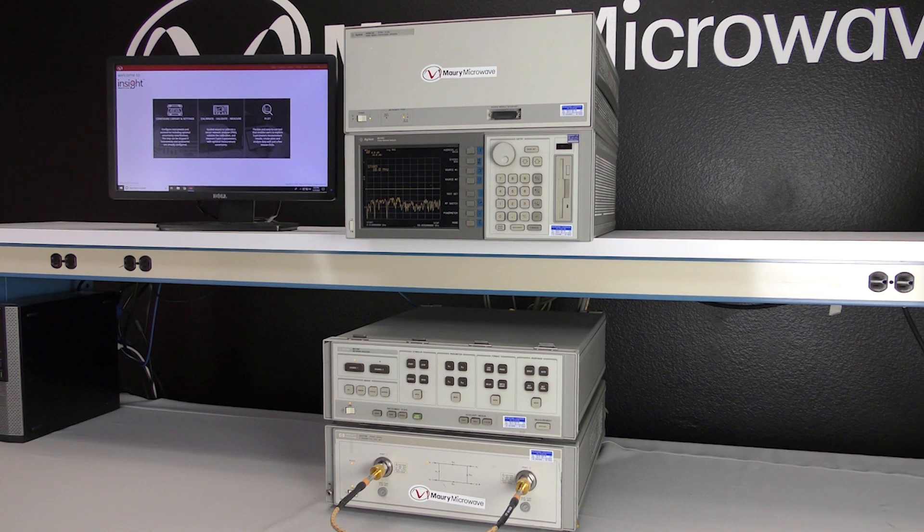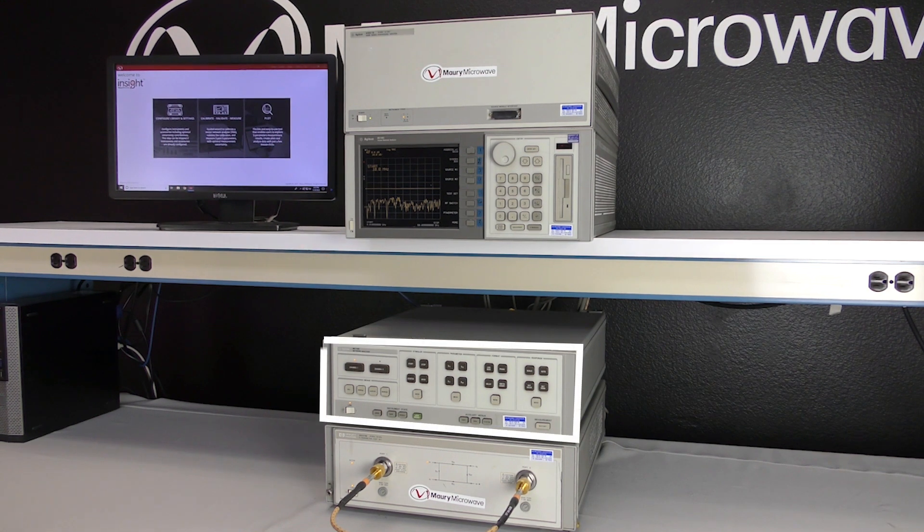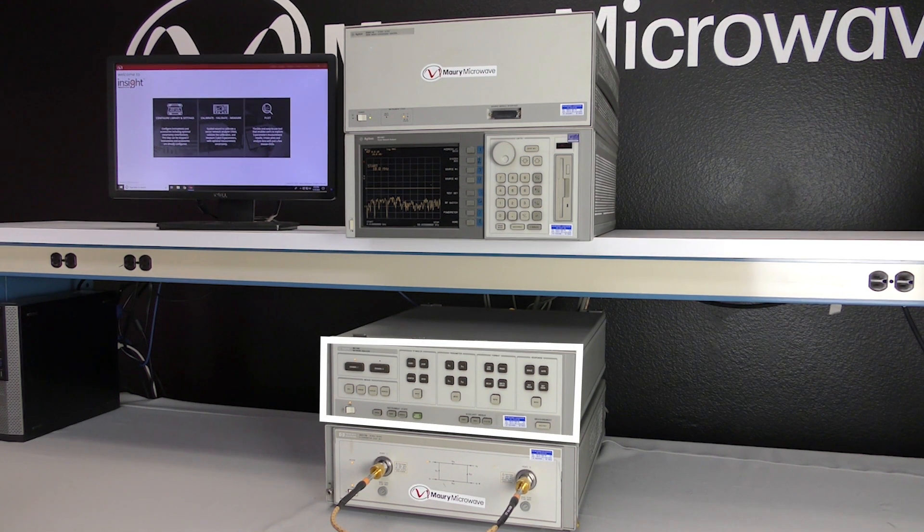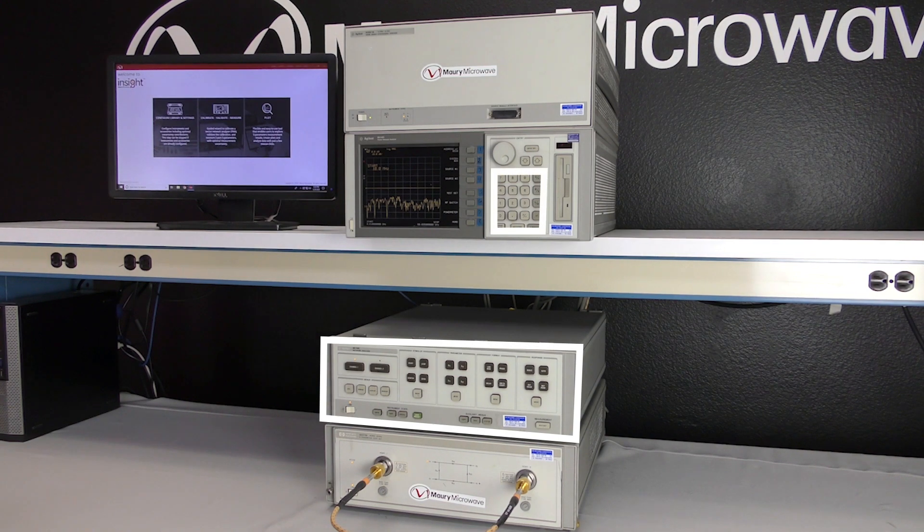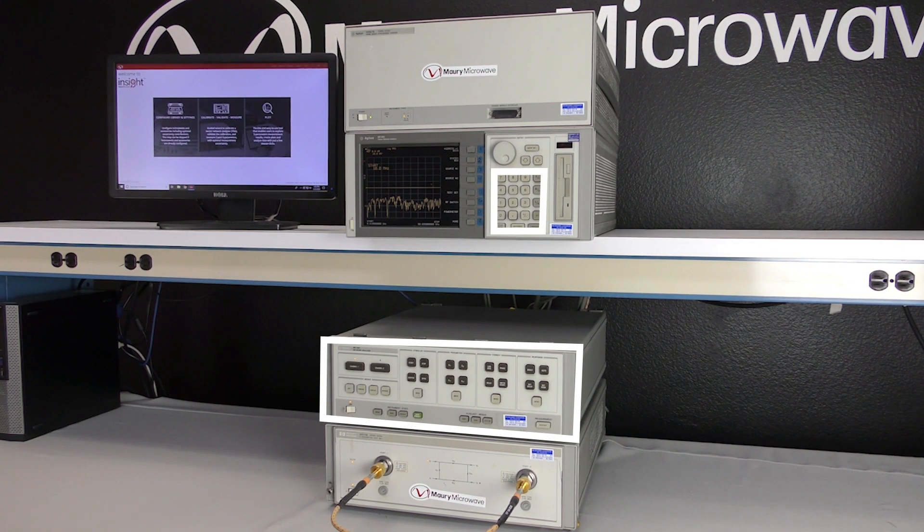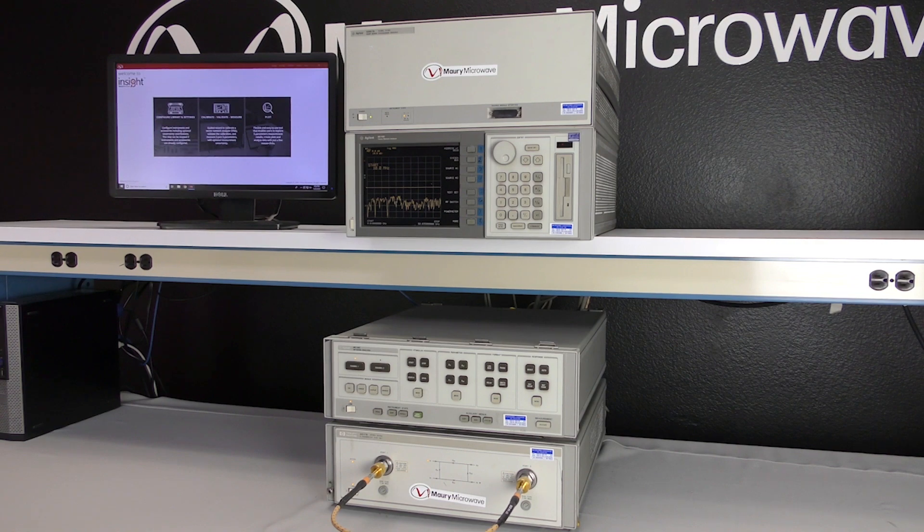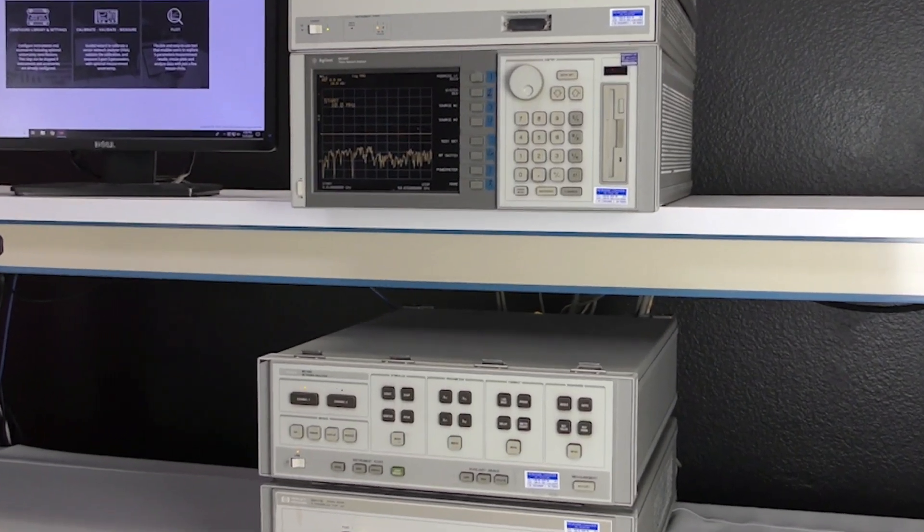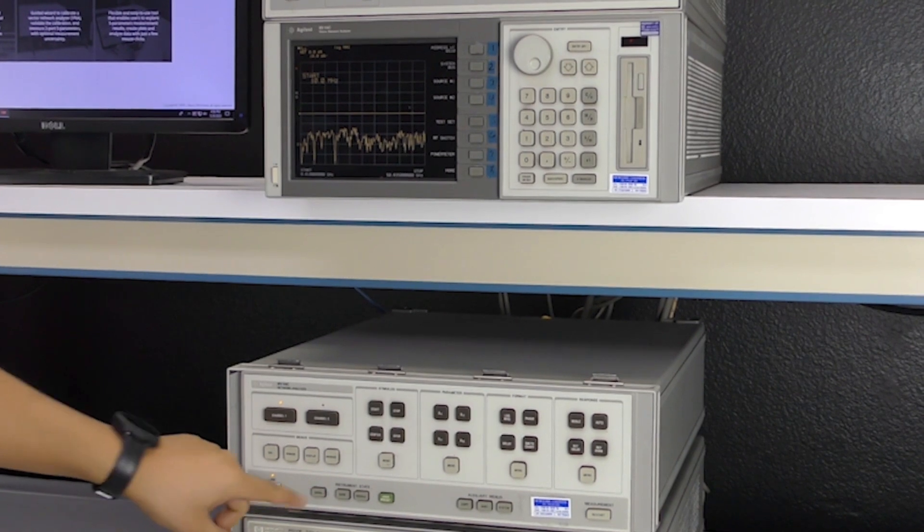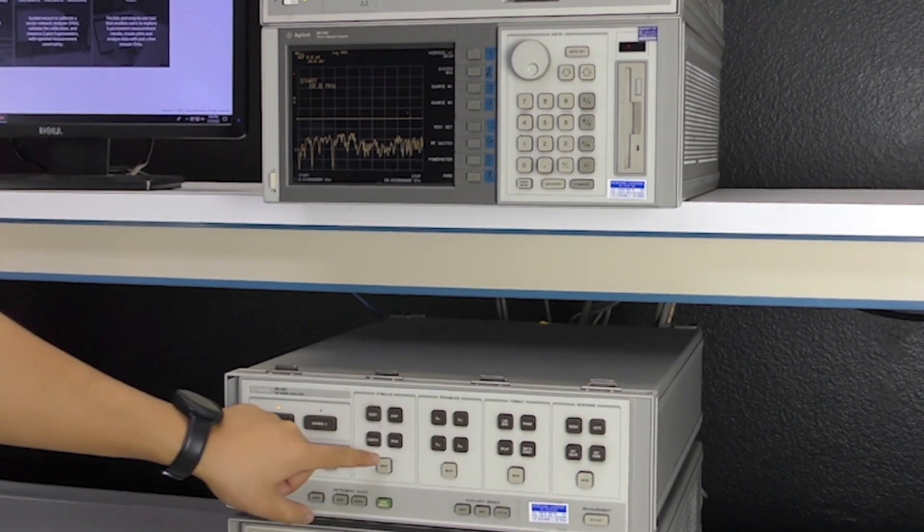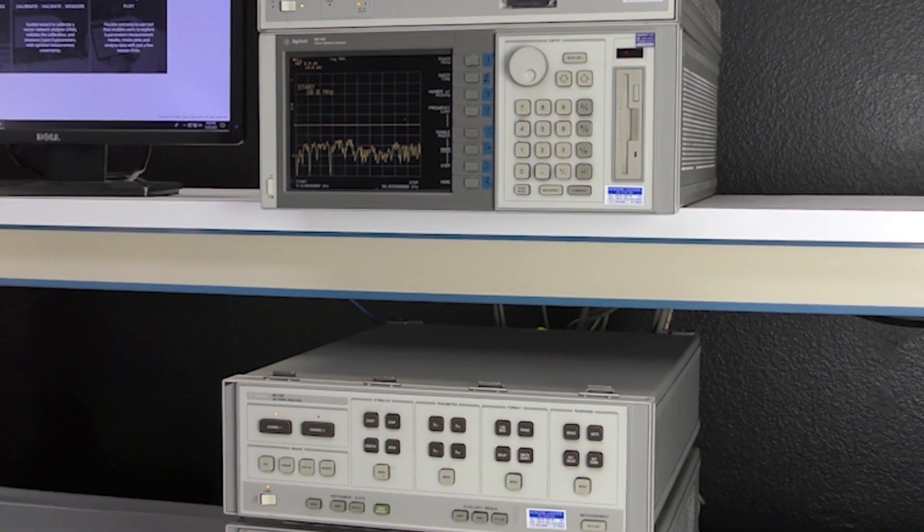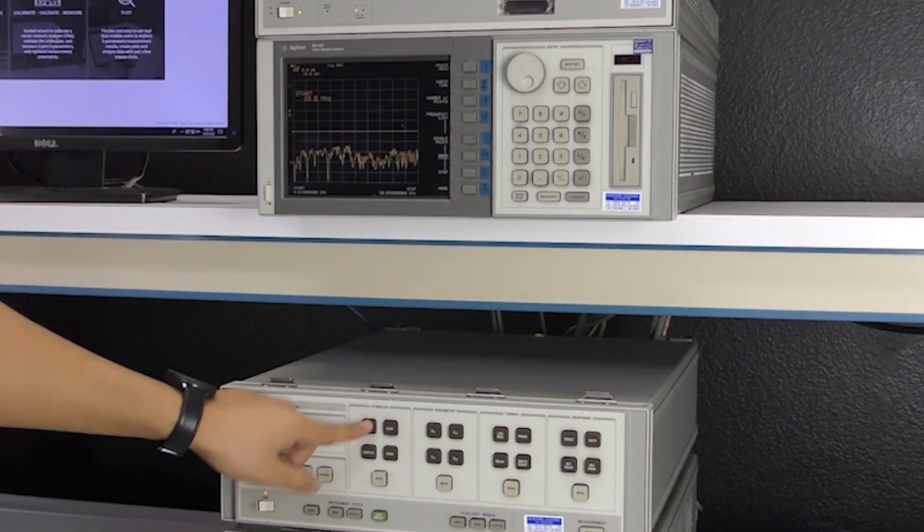Let's start off by taking a look at HP's 8510 VNA. This unit that I have here was in the warehouse and has broken touch keys, which will give you a headache while navigating the different menus. For those of you who are seeing the 8510 for the first time, you can see that there are a lot of buttons and menus to navigate through, from setting the source in the local menu to setting the power level and frequency range in the stimulus menu. The list doesn't stop there either.